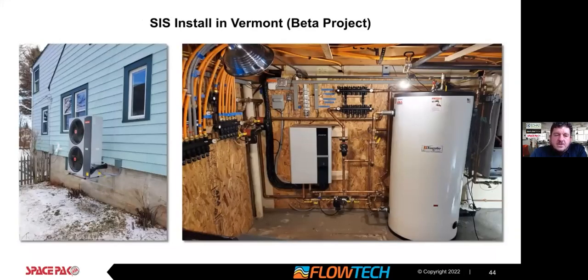Some more application photos here. I mentioned it's very important on the split units when you're in low ambient to get them off the ground. The units, both the monoblocks and the split units, they weep condensate. The condensate doesn't need to be treated. When it goes into defrost mode, there's quite a volume of water that comes off the units. And so when you have an area with snow and freezing conditions, you want to be able to get those units up off the ground, so it doesn't get buried with the buildup on that condensate.